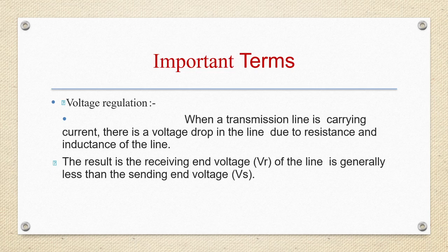Okay, so output is not equal to input because of this voltage drop. So the result is that the receiving end voltage of the line is generally less than the sending end voltage. The receiving end voltage I am representing by VR, and the sending end voltage is represented by Vs. This voltage drop Vs minus Vr in the line is expressed as a percentage of receiving end voltage Vr, and it is called voltage regulation.